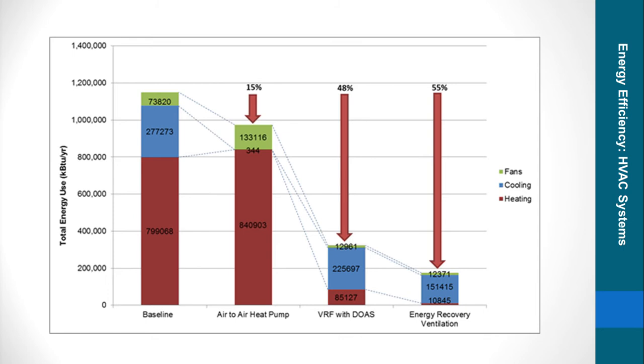Three types of HVAC systems were tested in the energy model. Rooftop terminal AC units were used for the baseline as required by ASHRAE 90.1. Next, a traditional air-to-air heat pump was tested, which eliminated the cooling load and reduced the overall energy used by 15%. Then, a variable refrigerant flow system with a dedicated outdoor air system for ventilation was tested, which reduced the overall energy used by 48%. When an energy recovery ventilator was added to the VRF with DOA system, the overall load was reduced 55% from the baseline.